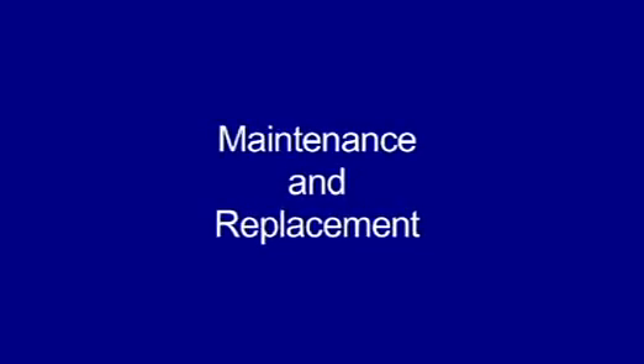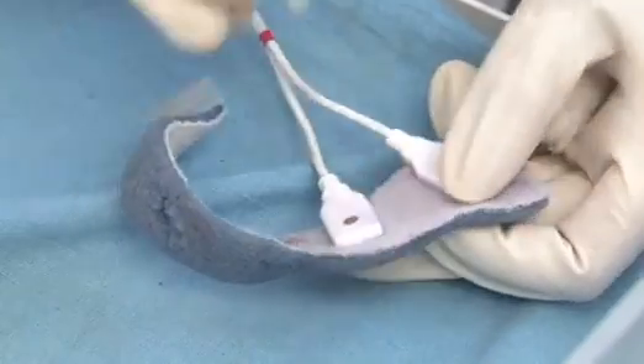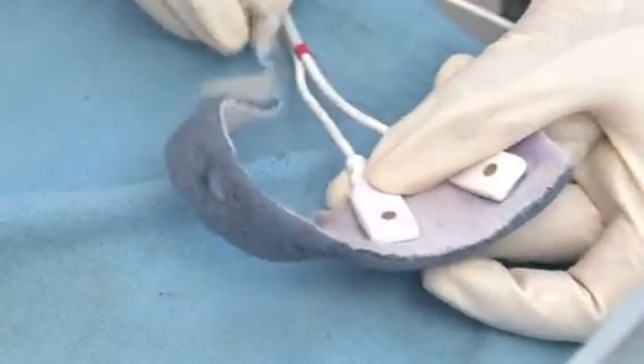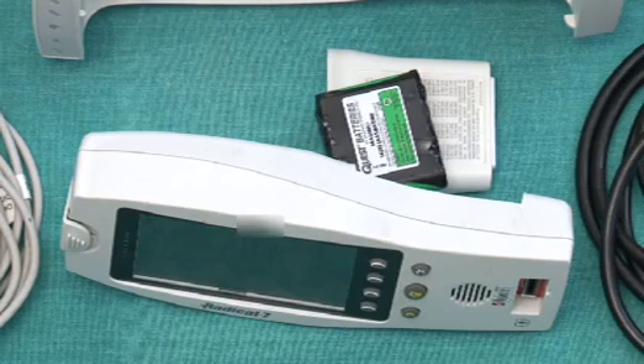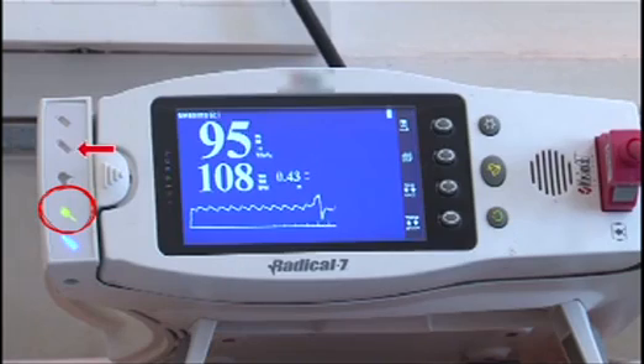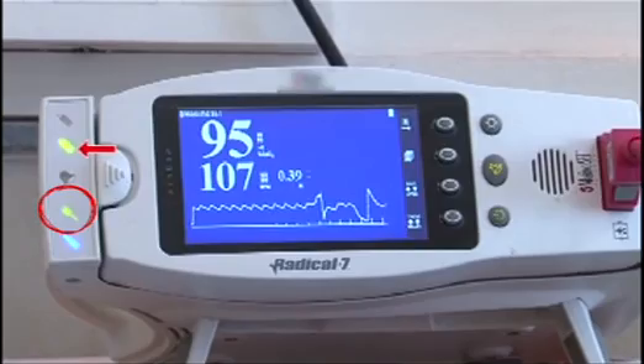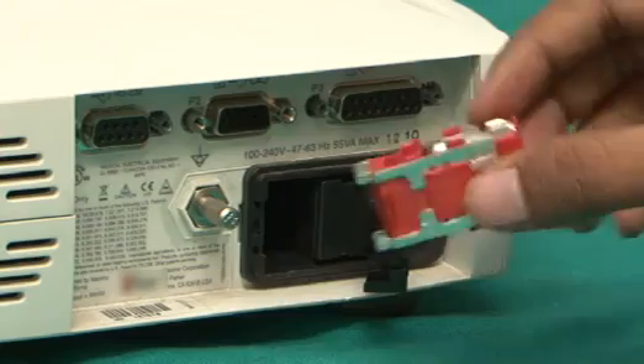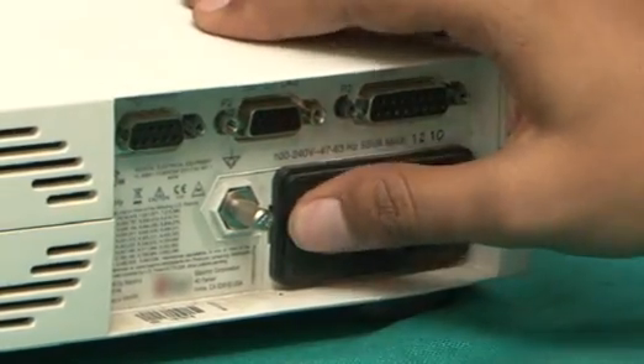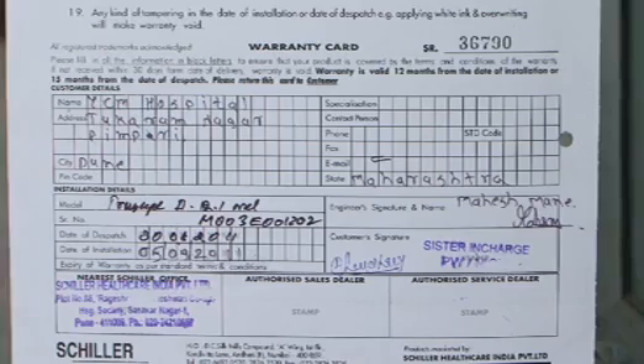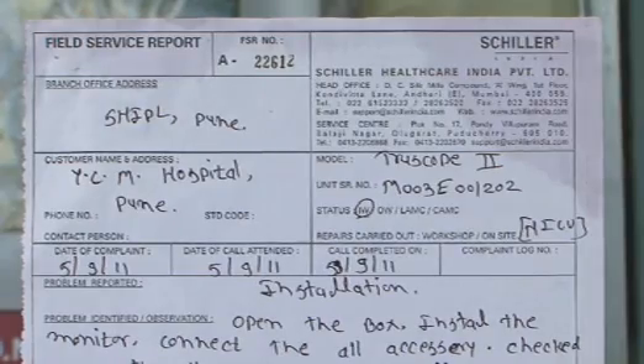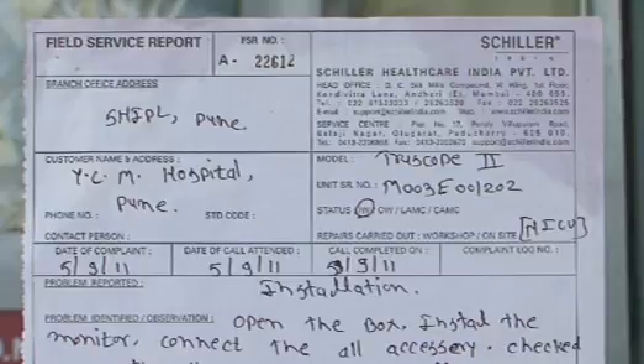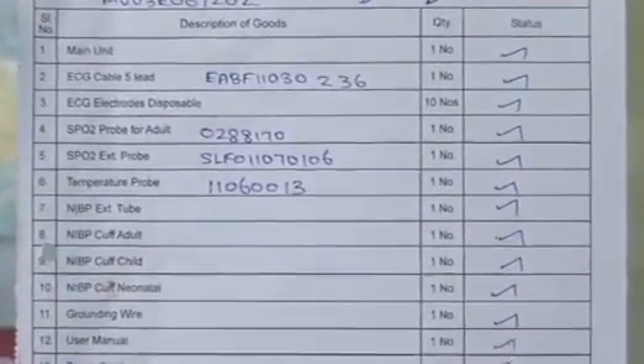Maintenance and replacement. Clean the reusable probe after each use. Clean the monitor surface regularly. Recharge the battery as necessary if low battery alert light is on. Replace the fuse and power module as necessary. Keep warranty card, AMC card and batch number and papers for parts replacement carefully for reporting failures.